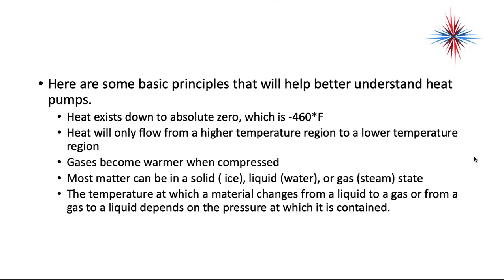So let's talk about some basic principles that will help us better understand this concept. Heat exists down to an absolute zero temperature. Absolute zero is negative 460 degrees. So heat exists in the air down to absolute zero. Gases become warmer when they're compressed, and we see that in the compressor side of any refrigeration system. When you compress it and raise the pressure, the gas becomes warmer. Most matter can be in a solid state, like ice, a liquid state, as in water, or a gas state, as in steam. The temperature at which material changes state from a liquid to a gas or from a gas to a liquid depends on the pressure at which it is contained.